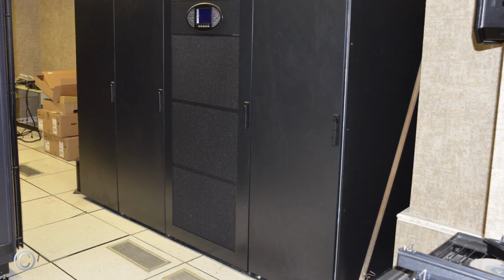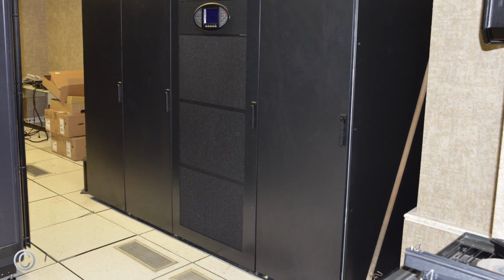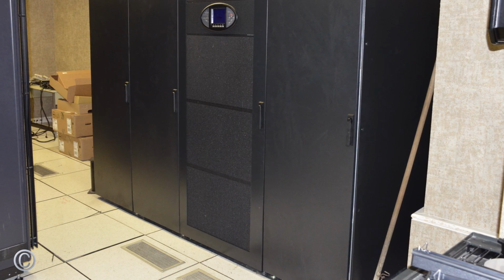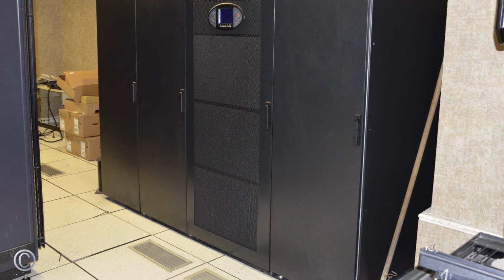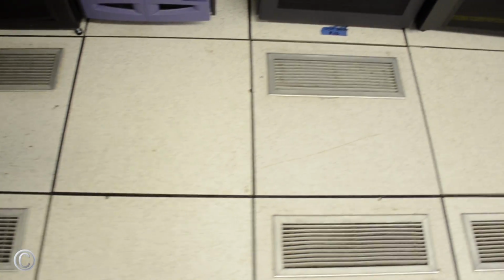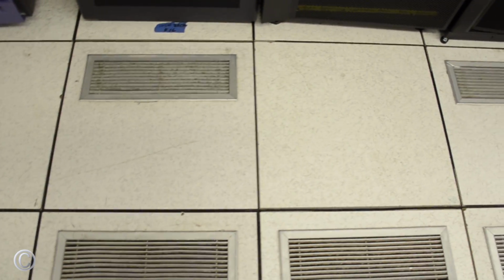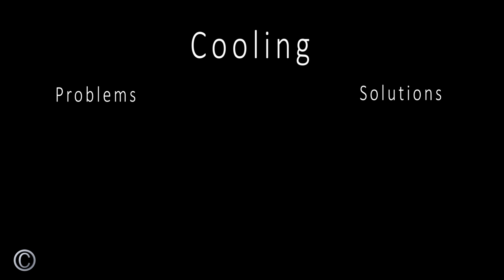The main issue with cooling in the data center is the mixing of the hot and cold air. This makes it difficult to achieve optimal temperatures for maximum efficiency from the CRAC units. These units perform best with the temperatures at their highest potential point. However, this is not an ideal situation for the servers since they need cool air to keep from overheating.